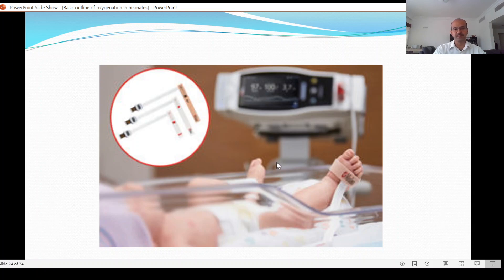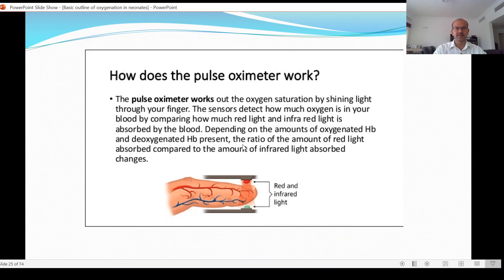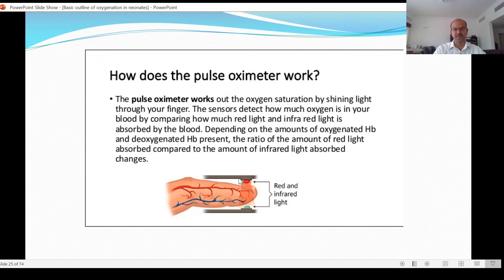The probe is placed on the foot or hand of the baby, sometimes on the earlobe if the baby is big enough. Different probe sizes are available. The pulse oximeter works by having a red and infrared light emitted from a light emitter on one side, with the detector on the other side — they must be opposing each other with nothing interfering. Movement artifacts can affect the reading, and external light may also interfere, so you may cover the probe with something opaque.